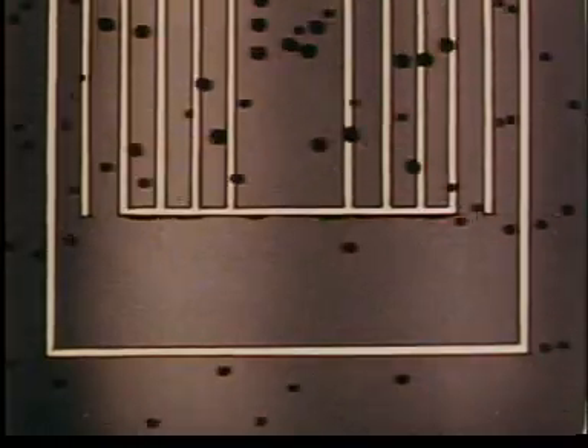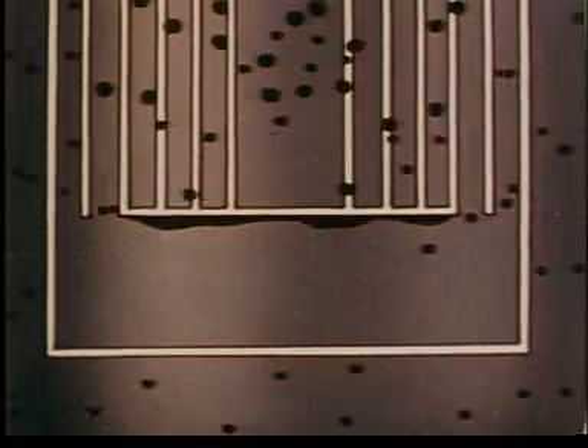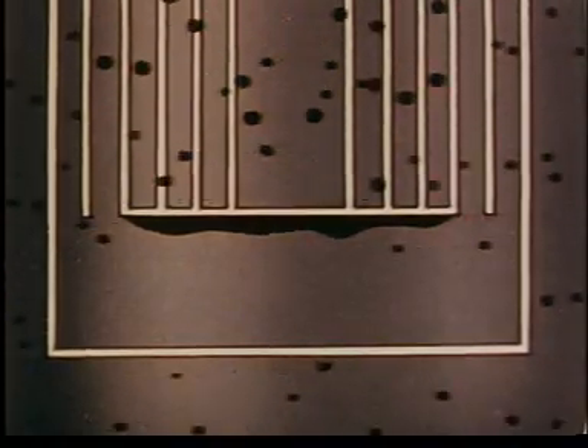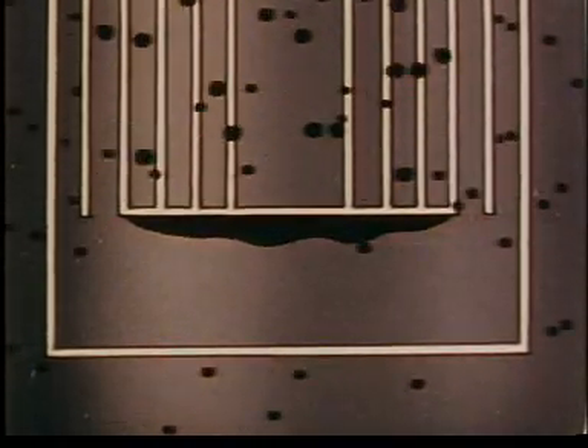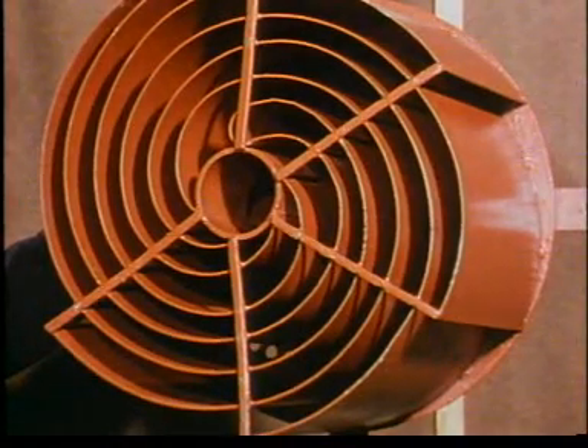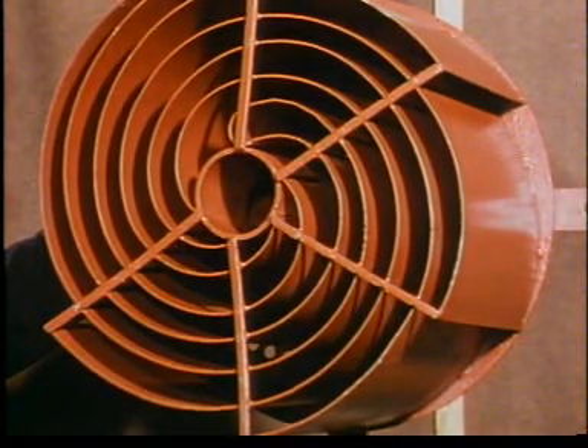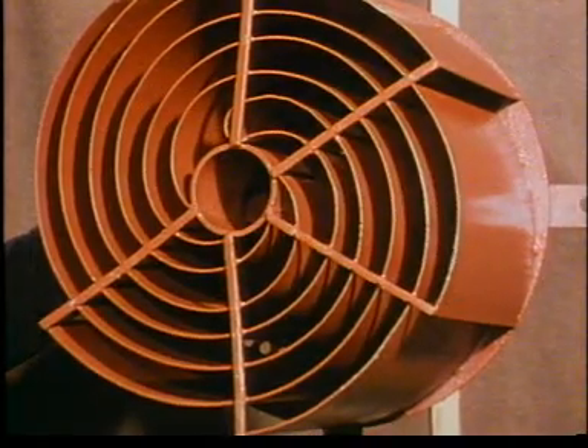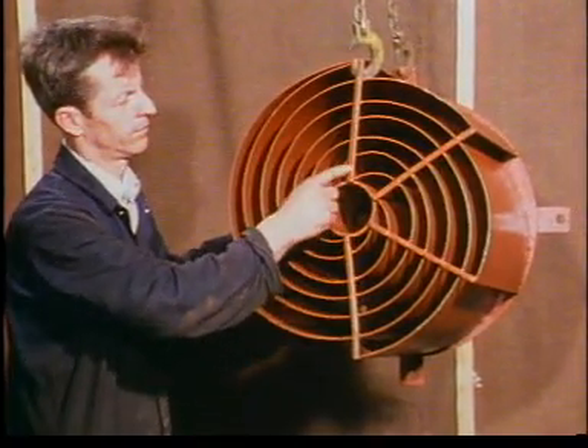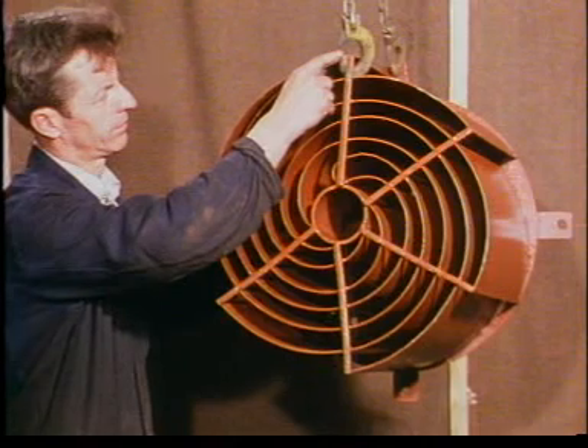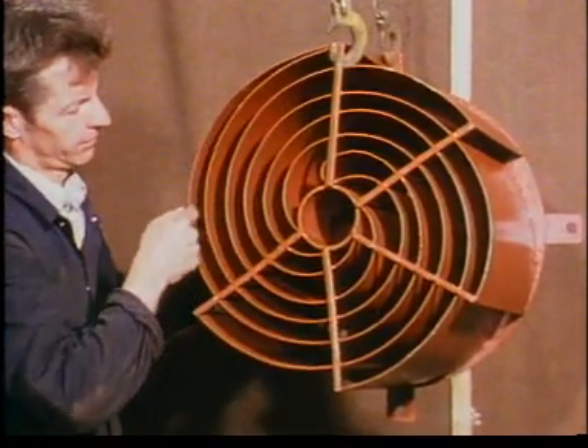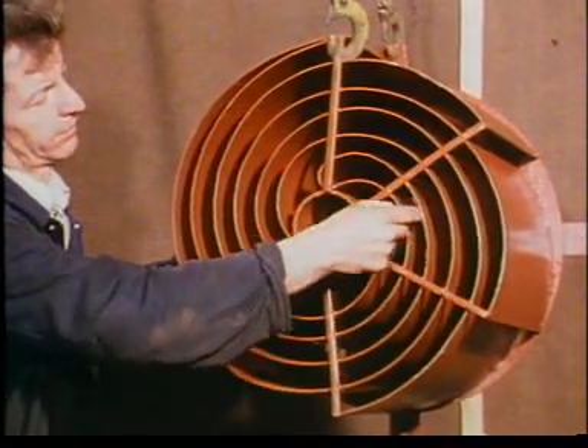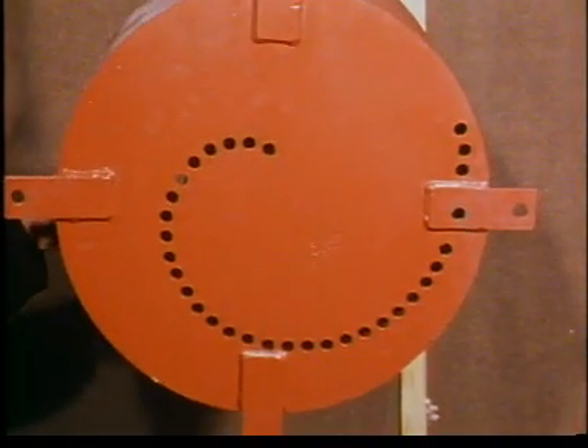When the mixture, containing comparatively little oil at this stage, is flowing under the base plate of the spiral ducts, small amounts of oil will still be separating out from the water and will float up and could be trapped by the base plate of the spiral ducts. To release this oil, holes, slots or internal piping are arranged to allow such trapped oil to flow upwards. In this type of element, one of the spiral ducts is sealed at both ends, though open at the top. The base plate under this duct has holes drilled through it throughout the length of the spiral.